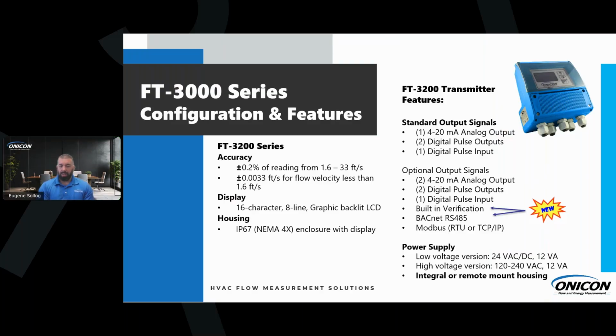Another option with both these transmitters is the remote mount housing. So we could have this mounted straight on the meter, like in the previous pictures, or we could have this remote mounted somewhere else in your mechanical space. With this one, the 3200 being a more powerful and accurate transmitter, this can actually go to runs of 200 feet away from that flow meter body. We can go further, but we need to add a signal amplifier.